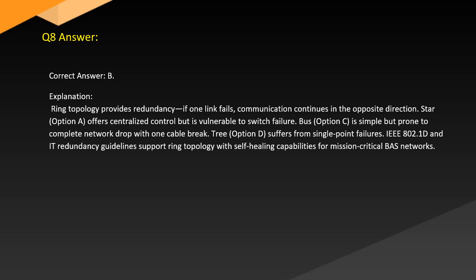Answer. Correct answer: B. Explanation. Ring topology provides redundancy. If one link fails, communication continues in the opposite direction. Star, option A, offers centralized control but is vulnerable to switch failure. Bus, option C, is simple but prone to complete network drop with one cable break. Tree, option D, suffers from single-point failures. The redundancy guidelines support ring topology with self-healing capabilities for mission-critical BAS networks.